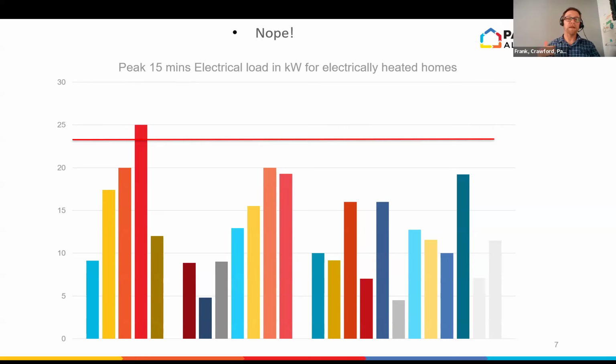line, peak line, and it included in the 25 kilowatts, 8 kilowatts of electric vehicle charging. So if we break out electric vehicle charging from that, because we can control when an electric vehicle charges using what's called a circuit pauser load share device, then the vast majority of the buildings were in a 10 to 15 kilowatt, 15-minute peak load range.